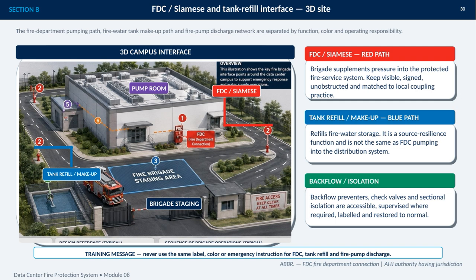The slide also calls out backflow protection and isolation. Backflow preventers, check valves, and sectional isolation points need to be accessible, labeled, supervised where required, and returned to their normal operating condition after use. The practical training rule is simple. Never use the same label, color, or emergency instruction for FDC, tank refill, and fire pump discharge. AHJ means authority having jurisdiction.